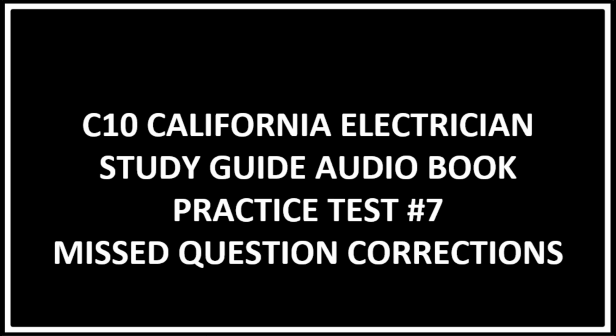Question 29. Switches, cutout or other equipment at 600 volts installed in a room or enclosure, where exposed live parts are at 600 volts, must maintain a 4-foot clearance between installed equipment and exposed live parts.